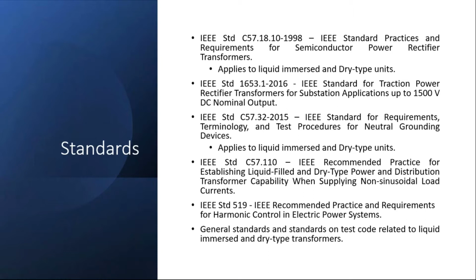This standard is very detailed. It covers all the service conditions, usual and unusual, then rating data requirement. Then we have impedance and commutating impedance requirement and the circuit types. And a very important thing in this standard is it covers the harmonics requirement and the loss calculations for the transformer to withstand those harmonics. And also it has the details of testing requirement. So for these transformers, you need to feed in additional losses based on the harmonics, and those are covered in the standard.